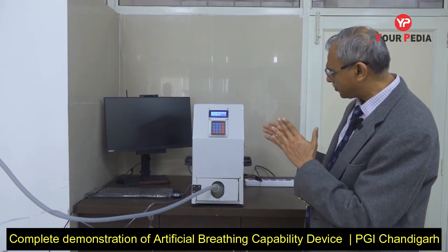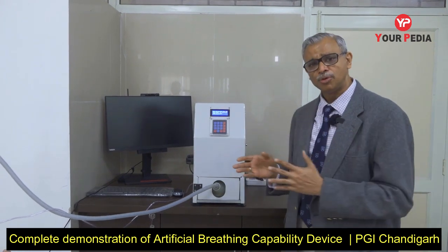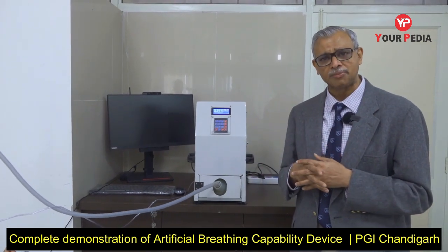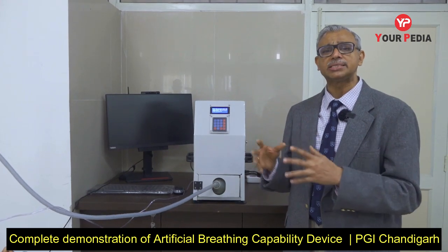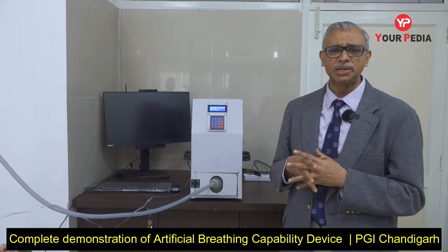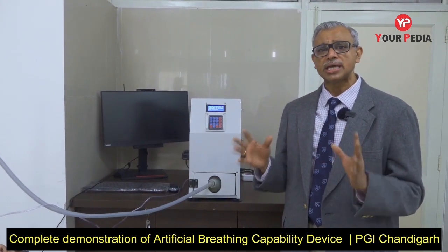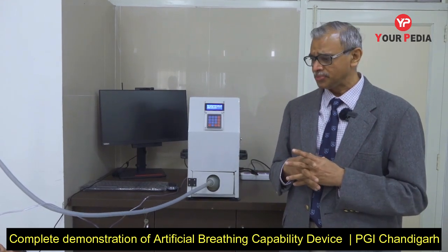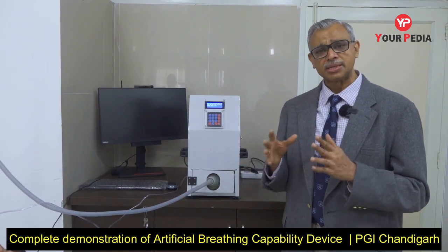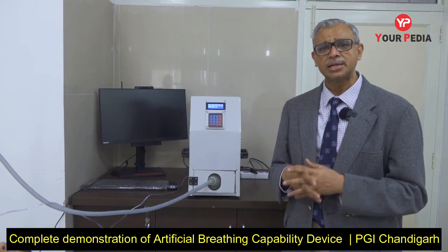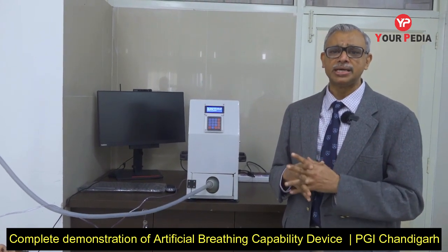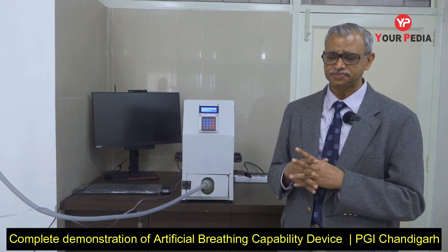This device performed very well with an adult-sized Ambu bag, which is about 1.5 liters capacity, followed by a pediatric-sized Ambu bag, which is about 500 milliliters of capacity. So 2 cycles of 60-day non-stop testing, and after that, the results were submitted to a prestigious international journal, published, and therefore is now deemed to be acceptable.